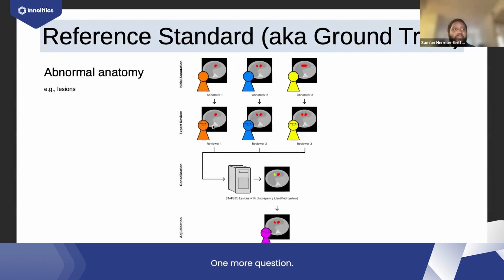Okay, thank you. One more question, sorry. I was wondering, because you had said there's really no set way to do this process, are there any guidelines, or is it just that they want experts to review it? I mean, there is the CADe guidance, I'm forgetting the name of it. It's not on the screen. Computer-Assisted Detection Devices Applied to Radiology Images and Radiology Device Data. That one does have a little bit of guidance on establishing ground truth, but it's still pretty high level.